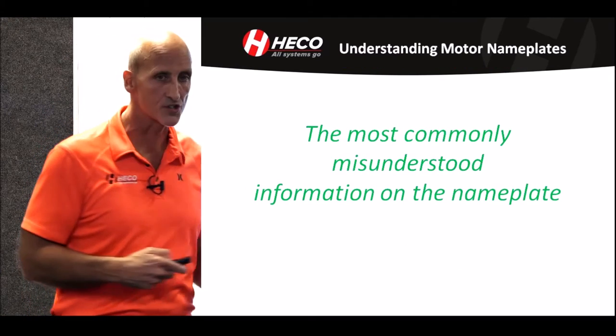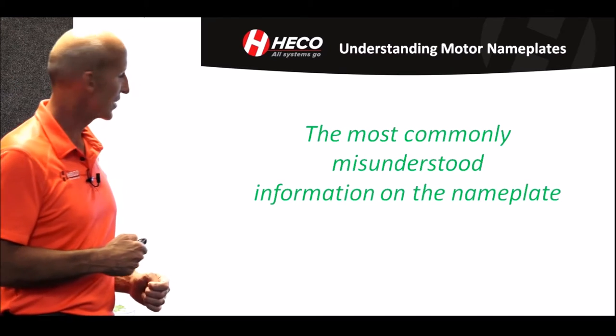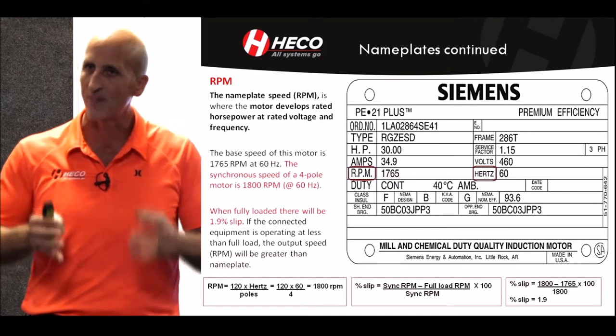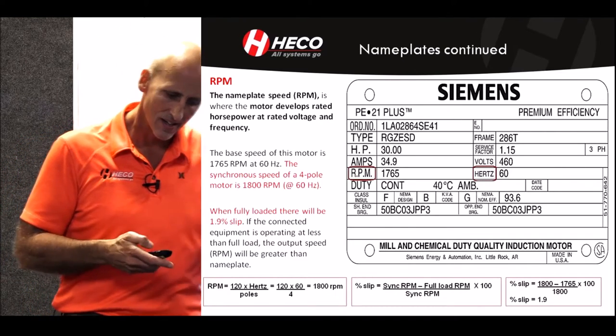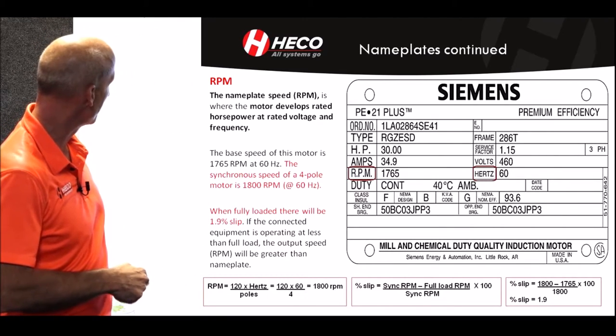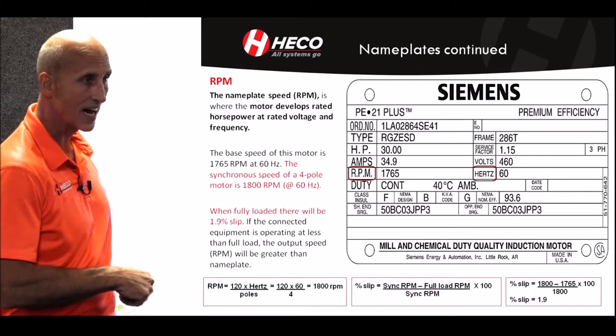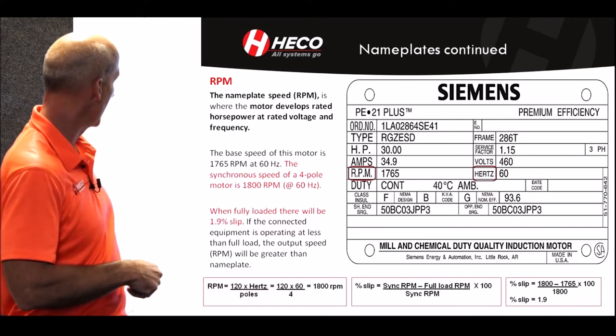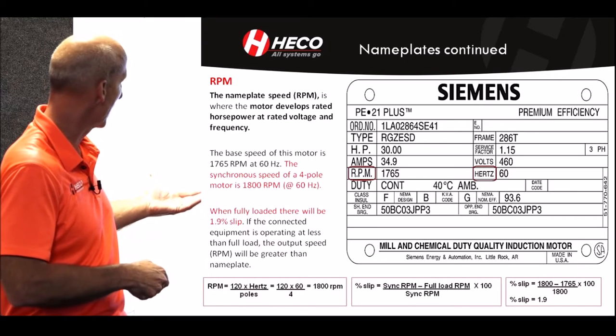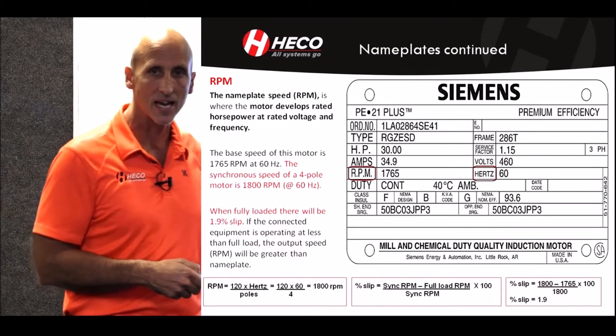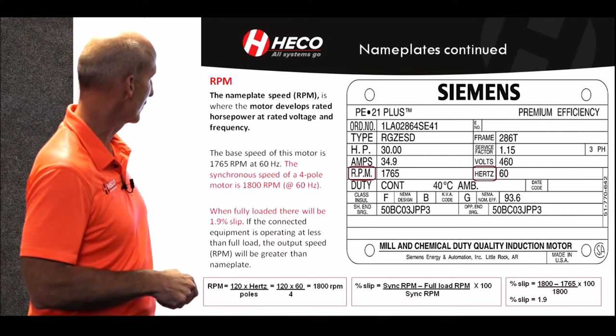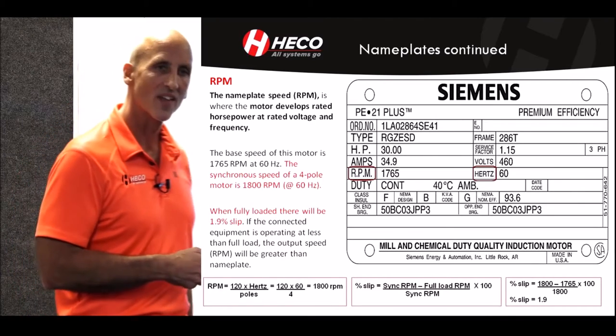The most commonly misunderstood item on the nameplate: the nameplate is interesting because there's a lot of information there, and a lot of people don't understand what the information really says—and then maybe misapply the motor. The RPM is defined by this formula: 120 times the frequency. At 60 hertz with a four-pole machine, that gives you 1,800 RPM—that's the synchronous RPM. To calculate what the slip RPM is, you have to use the other formula.